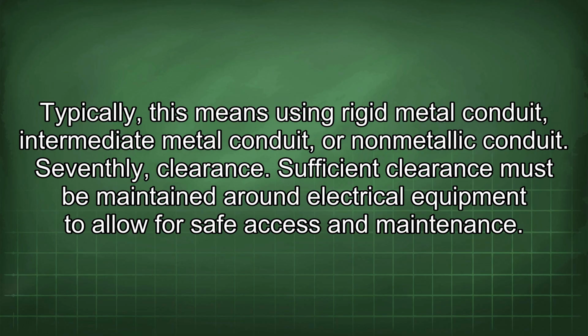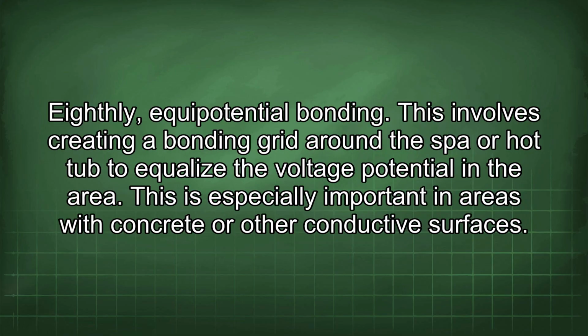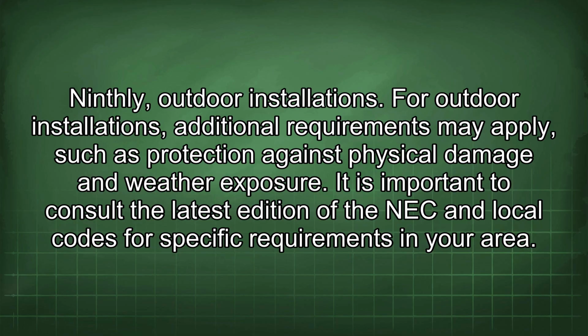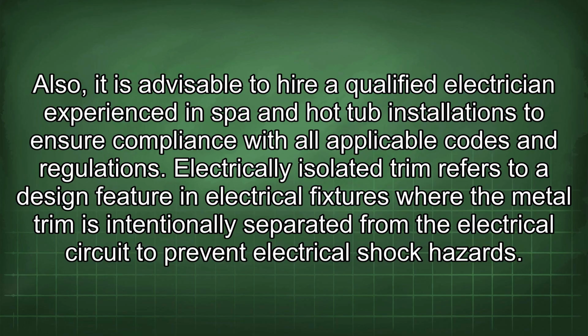Typically, this means using rigid metal conduit, intermediate metal conduit, or non-metallic conduit. Seventhly, clearance. Sufficient clearance must be maintained around electrical equipment to allow for safe access and maintenance. Eighthly, equipotential bonding. This involves creating a bonding grid around the spa or hot tub to equalize the voltage potential in the area. This is especially important in areas with concrete or other conductive surfaces. Ninthly, outdoor installations. For outdoor installations, additional requirements may apply, such as protection against physical damage and weather exposure. It is important to consult the latest edition of the NEC and local codes for specific requirements in your area. Also, it is advisable to hire a qualified electrician experienced in spa and hot tub installations to ensure compliance with all applicable codes and regulations.